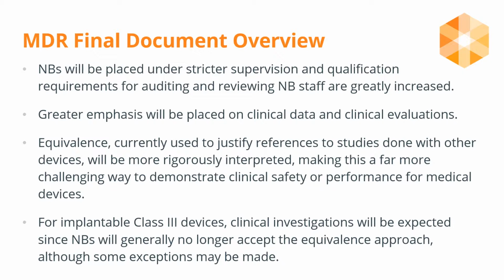There will be a greater emphasis on clinical data and clinical evaluations. Using equivalence, which is currently used to justify references to studies done with other devices, will be more rigorously interpreted and will be a more difficult way to demonstrate clinical safety or performance. For implantable Class 3 devices, clinical investigations will be expected, as the equivalence approach will generally not be accepted.